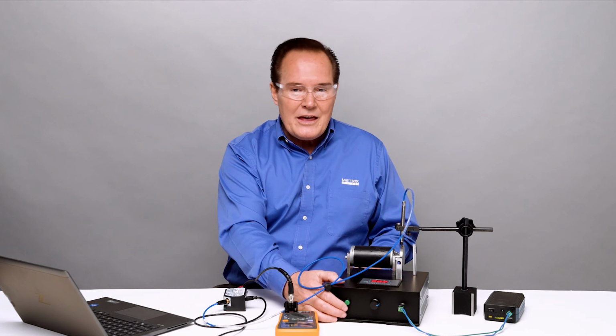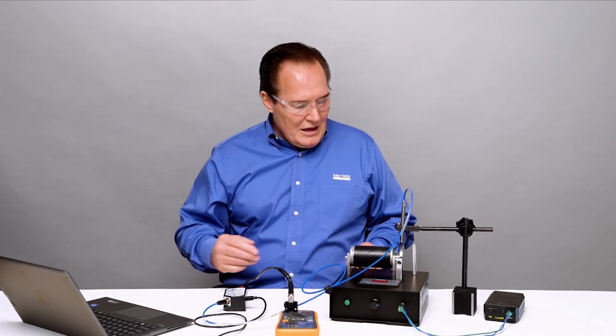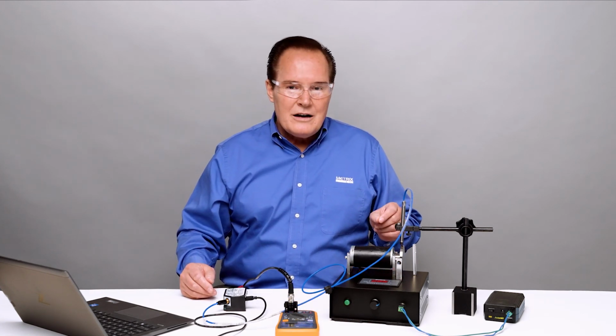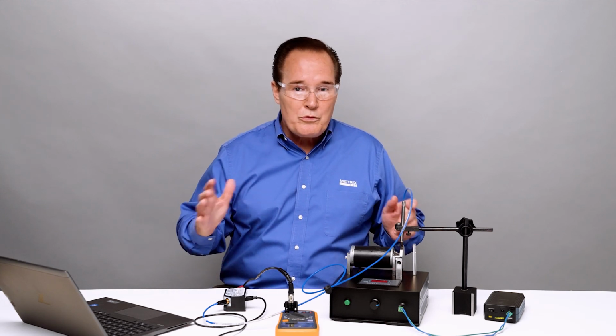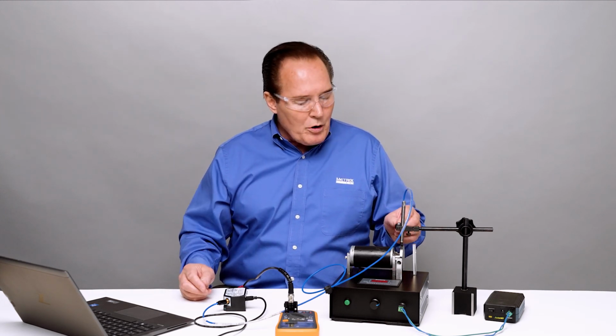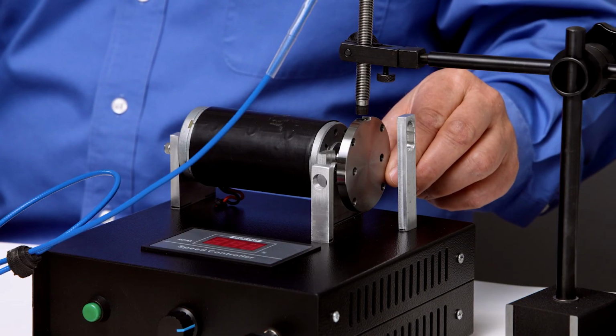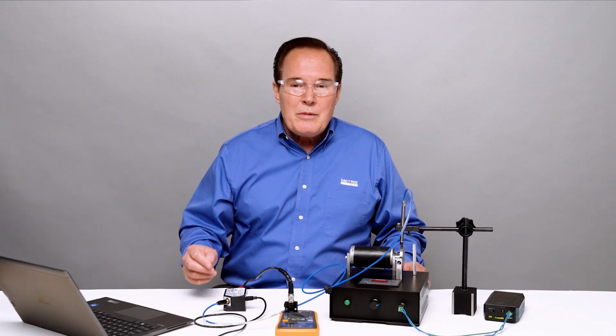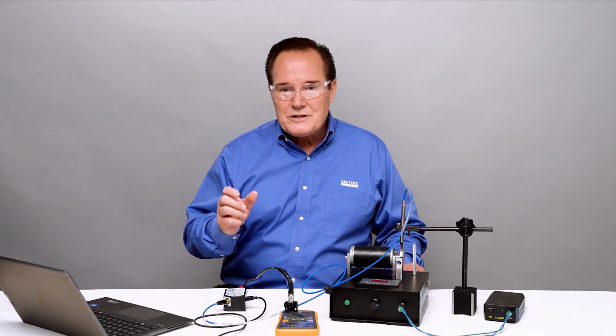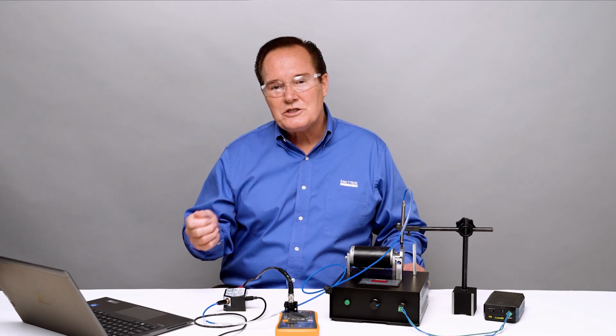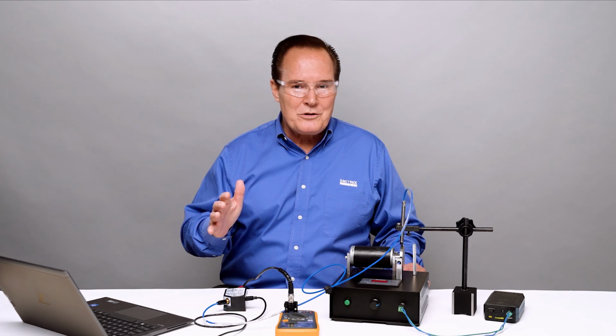First of all, we started with the probe nicely oriented with the notch, and then we went to the probe being askew the notch. In other words, due to a thermal growth problem or a thermal change, the probe is no longer lined up, and you can see that it's not very nicely lined up, but we can still get a good adequate pulse because we can change the scale factor in the Digital Proximity System. Now you never want to do this for a vibration sensor or a position sensor, or when you're using it that way for a thrust transducer or vibration, but for speed you can.